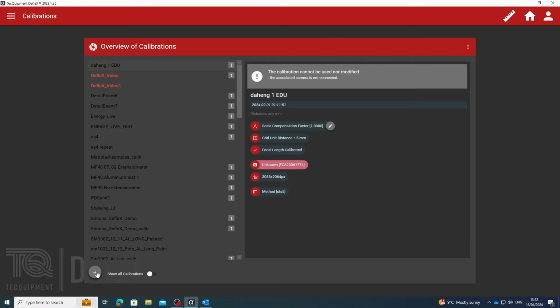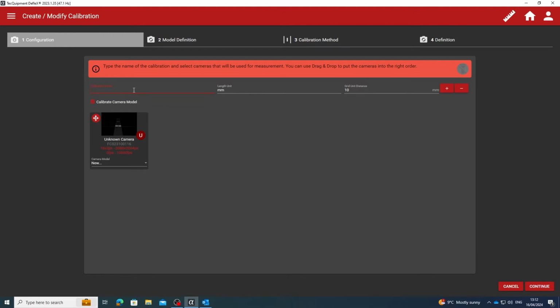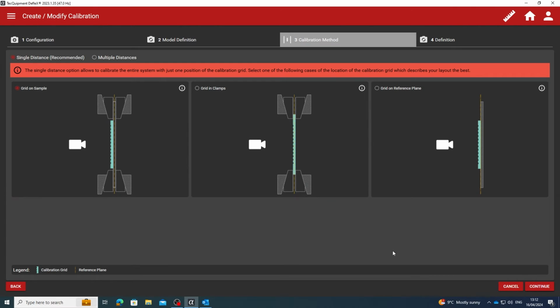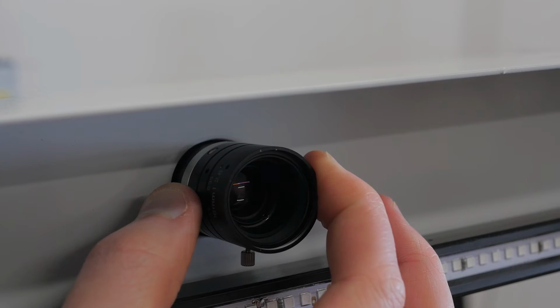Select the 2D calibrations, click on the yellow plus button to add a new calibration and select full calibration. Next, name the calibration, set the units used, and insert the grid unit distance. On the next page, the grid needs to be detected to establish a coordinate system and a pixel to millimeter ratio. Focus the lens on the specimen.